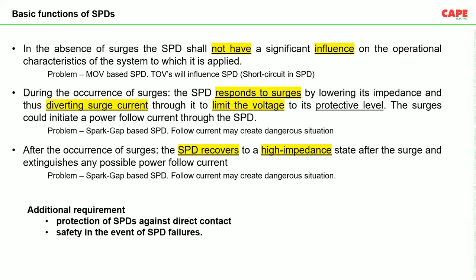First possibility is SPD can fail in an open circuit condition. In that condition, there is no problem. SPD is going to just disconnect itself from the system. Second possibility is SPD fails in a short circuit mode.